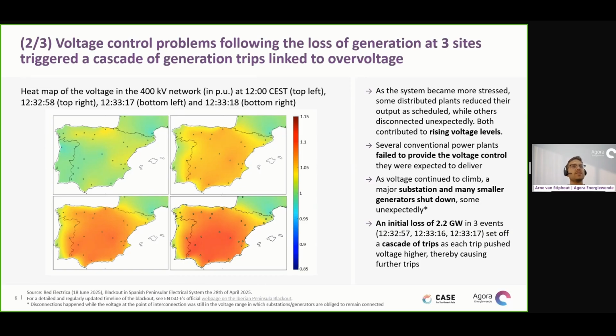So we see in the top right the voltage levels. Here 1 means we're at 100%, at the nominal level. 1.1 means we're 10% above, which is the limit below which you should typically still be operating in a safe zone. So we see that at 12:32:58, just after the first generation loss, there is an initial rise, and then the bottom two are the second and the third right after them, and then we see that this voltage goes beyond the typical thresholds.